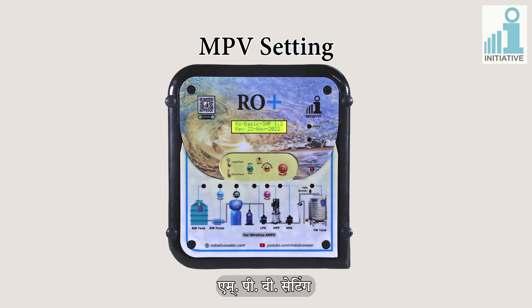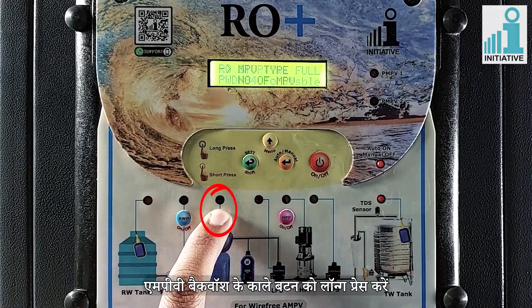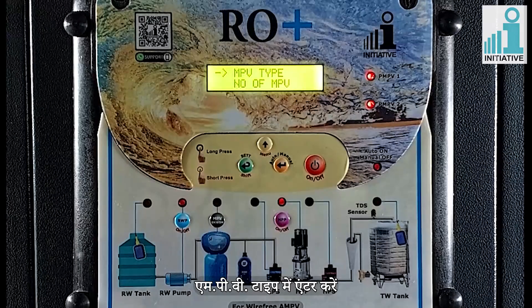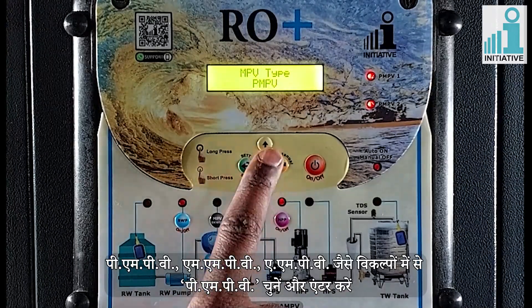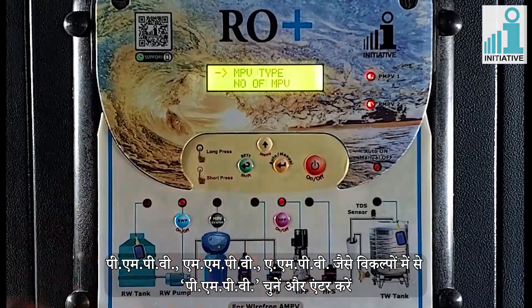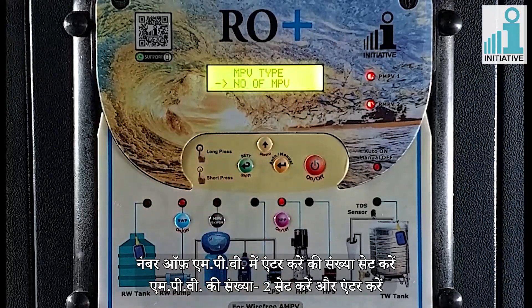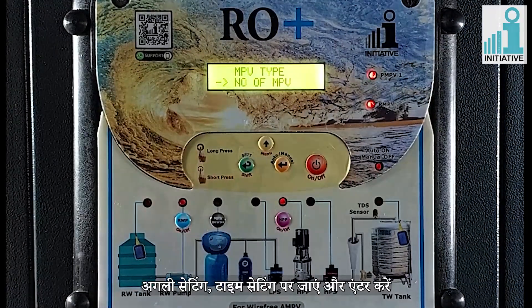MPV setting. Long press the black button of MPV backwash. Enter in MPV type. Select PMPV from the options like MMPV, AMPV, PMPV and enter. Enter in number of MPV. Enter the number of PMPV as 2 and enter. Go to the next setting of time setting and enter.